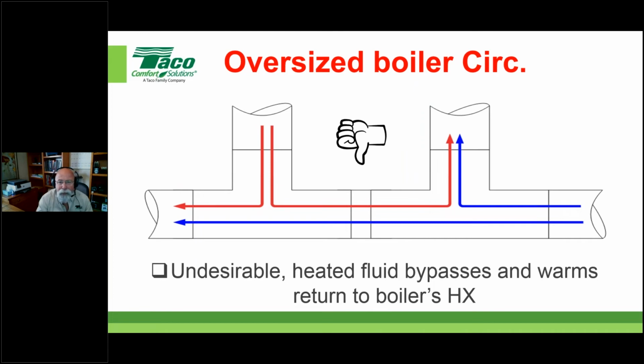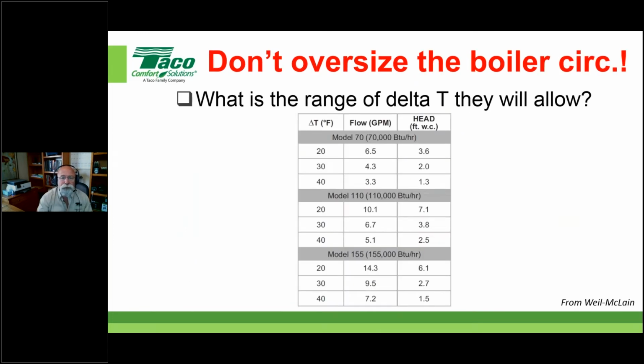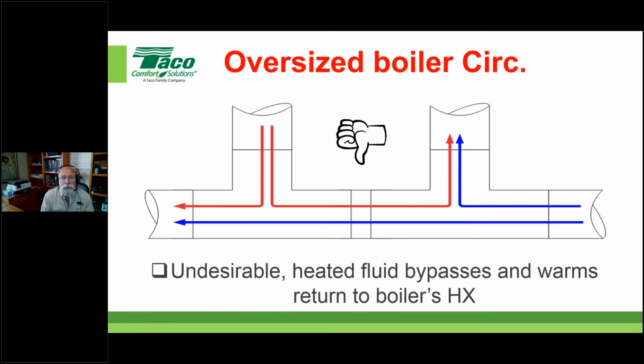Did have one other question about closely spaced tees. What does the up to 12-inch max refer to in 4 pipe diameters up to 12 inches max? 3-inch pipe. How many people are doing 3-inch pipe on this webinar right now? On a regular basis, your boilers have secondary headers that are 3-inch. That would be the 12 inches, right? 4 pipe diameters times 3 inches, 12 inches. So again, closer the better.